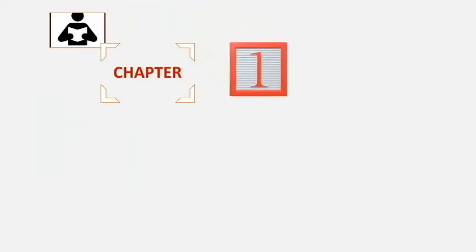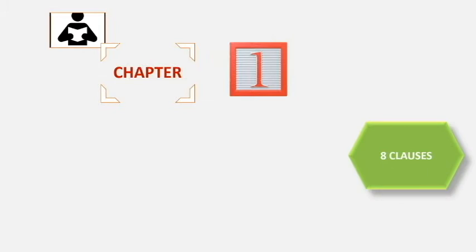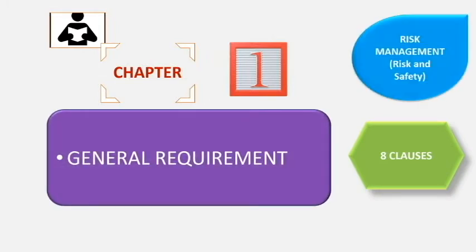Chapter 1 contains eight clauses and deals with general requirements. It covers the risk and safety that the manufacturer must comply with, safety and related risks for the intended user, risk management, post-market surveillance, the principles carried out for safety, and also transport and storage.